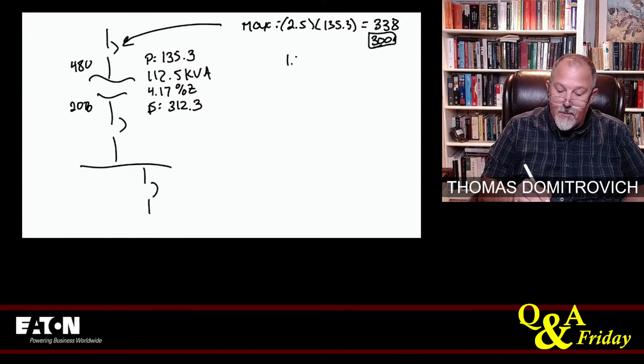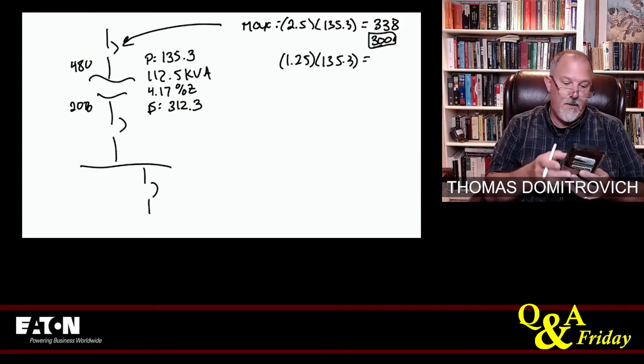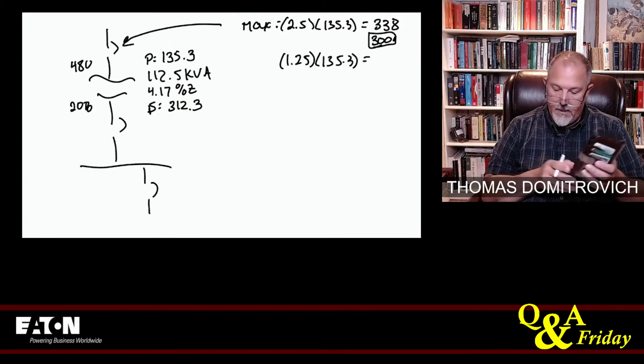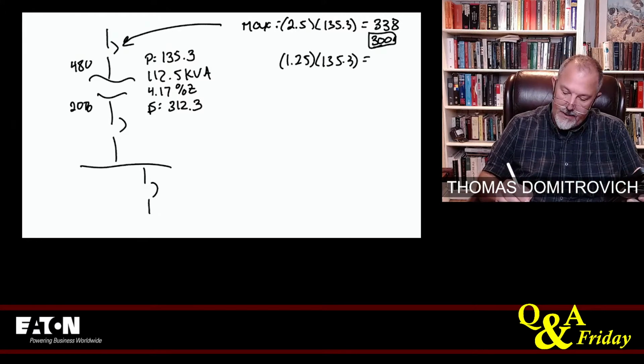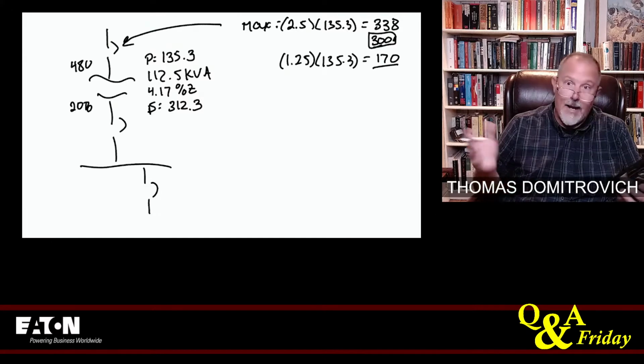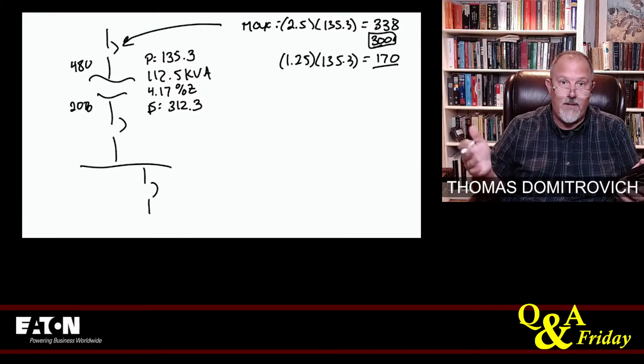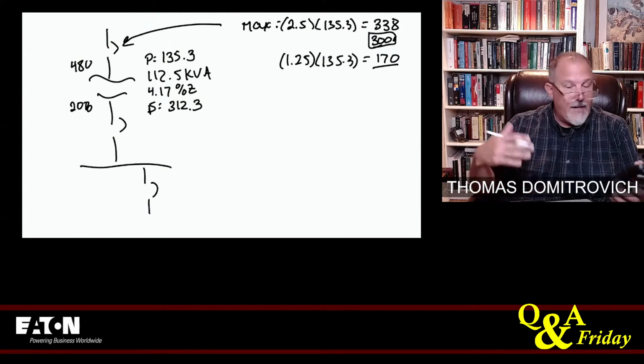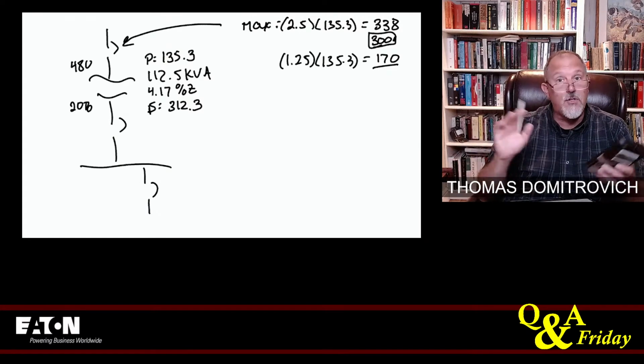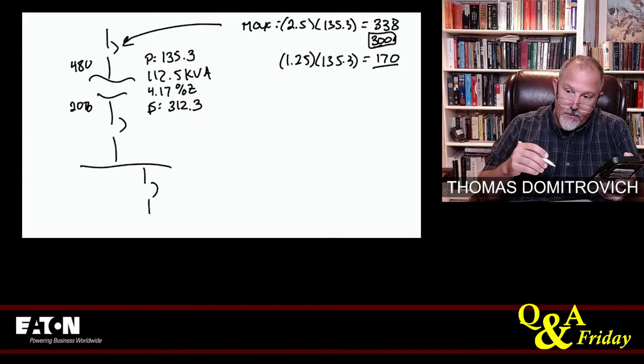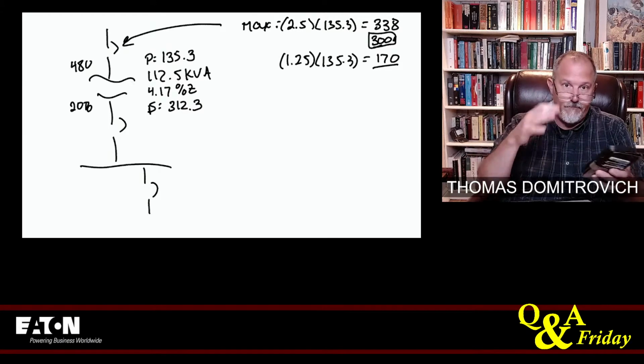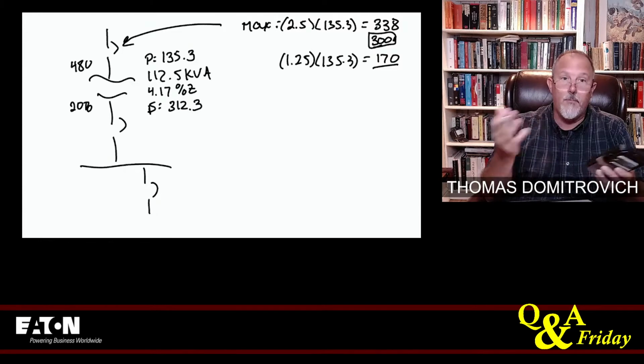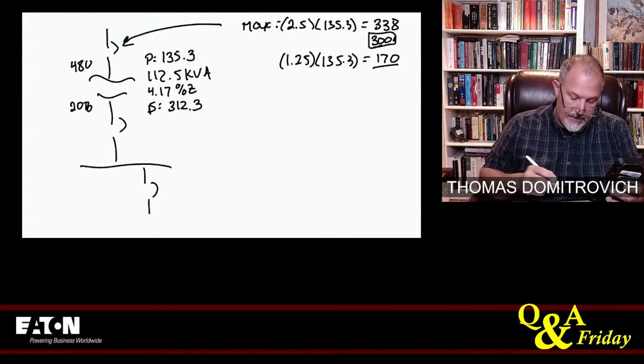What we typically use is 1.25, right? So 1.25 times 135.3 is 170. And I don't have to go to standard, so I can use a 170, if I can get whatever size breaker I'll get. That's our starting point. When we go to SKM, we'll see what breakers are available. We'll try to go with a thermal mag.